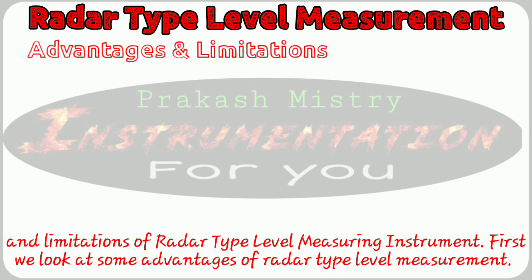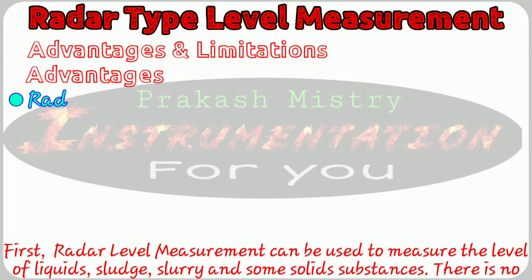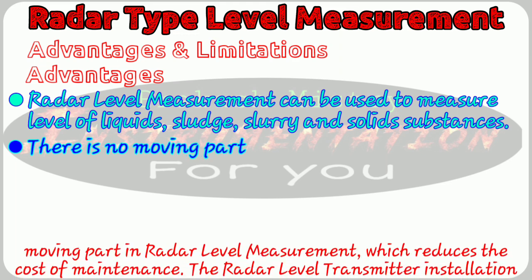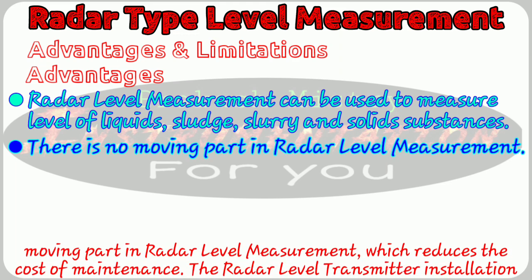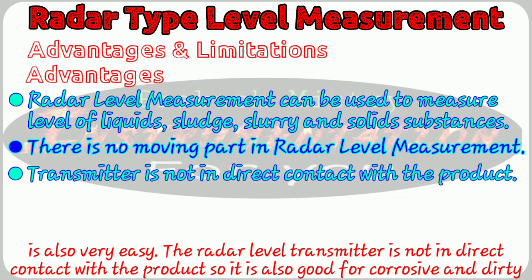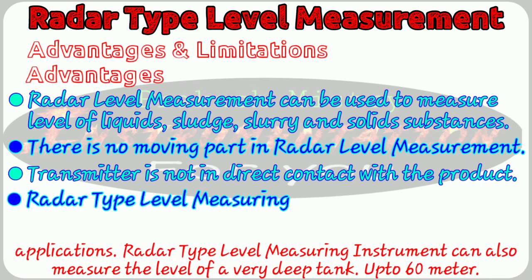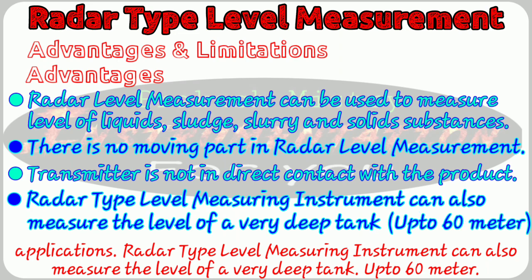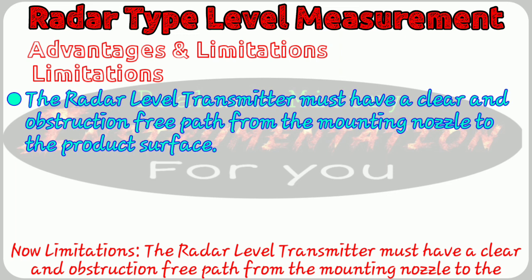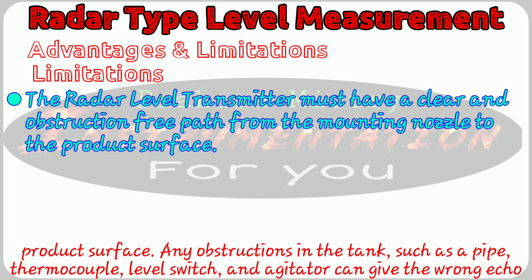Now let's move on to the advantages and limitations of radar type level measuring instruments. Advantages: radar level measurement can be used to measure the level of liquid, sludge, slurry, and semi-solid substances. There are no moving parts in radar type level measurement, which reduces the cost of maintenance, and installation is also very easy. The radar level transmitter is not in direct contact with the product, so it is also good for corrosive and dirty applications. Radar type level measuring instruments can also measure the level of very deep tanks, up to 60 meters. Limitations: the radar level transmitter must have a clear and obstruction-free path from the mounting nozzle to the product surface. Any obstructions in the tank such as pipes, thermocouples, level switches, and agitators can give a wrong echo signal.